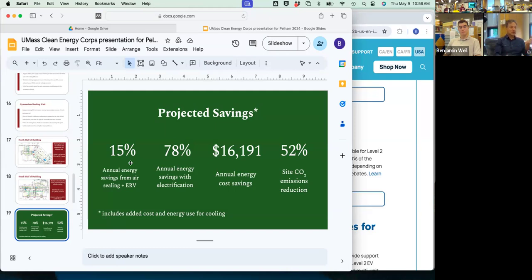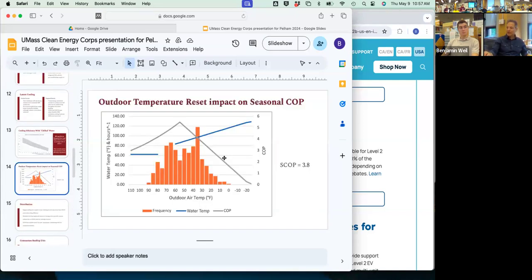Let's say you did the insulation in the roof and the air sealing. We calculated that you need 115 degrees at a design temperature of -5 degrees Fahrenheit. But with the air sealing plus the roof insulation, which we shouldn't even make a guess at, let's say we've cut 5 to 10% off. Well, that means your water temperature maybe is 105 degrees. That lowers this slope a bit, and the lower the water temperature, the higher the efficiency. So maybe your seasonal coefficient of performance, instead of being 3.8, goes all the way up to 4, which is basically competitive with geothermal. So little tweaks in water temperature, which are made possible by insulation, could have that effect.